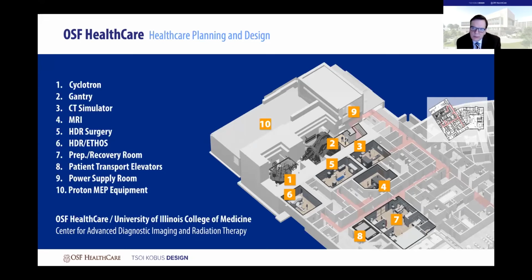We also had the problem in doing the high dose rate brachytherapy or implant radiation, where we're actually going in the operating room and putting needles or applicators into the patient to allow a very intense and miniaturized radiation source to move on a cable through those applicators and needles to really paint an ideal dose of radiation. We were doing 11 steps, 11 different places that the patient had to be to deliver that one dose of treatment.